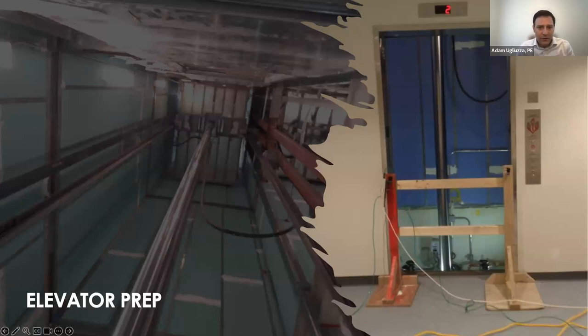Sometimes we need to use elevator shafts if we have a really tall building and a limited amount of staircases. Generally, if the building's leakier, we might have trouble pressurizing the top of the building, so the elevator shaft promotes that connection throughout the entire building. It's on the rare side that you need to do this, but on some buildings you might have to prepare in advance, which takes a lot of coordination. You need somebody competent with the elevator operation who can set it up in a way that's not going to damage it and not going to have any negative effects on the operation or safety during that test.